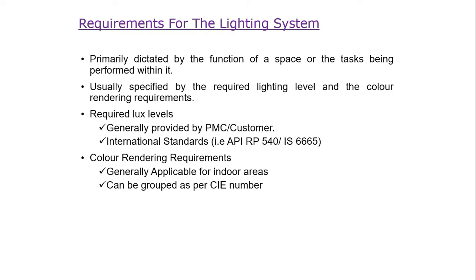In many areas there is a requirement that very fine granules have to be checked with respect to colour and quantity. For that area, a specific clean room or a specific design lighting has to be done. However, for a substation that requirement will not suit the purpose — the requirements are altogether a different purpose. The lighting design has to be designed based on the requirement of a substation, not a clean room requirement. That is a very, very important point.